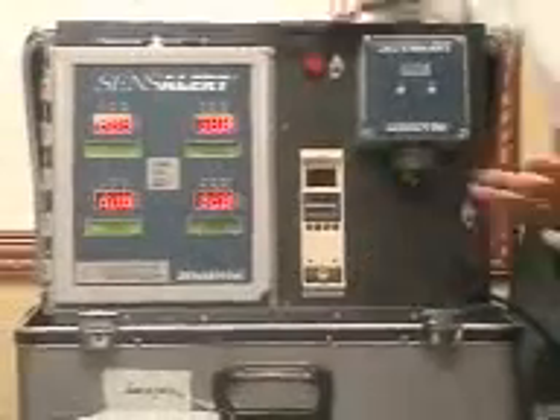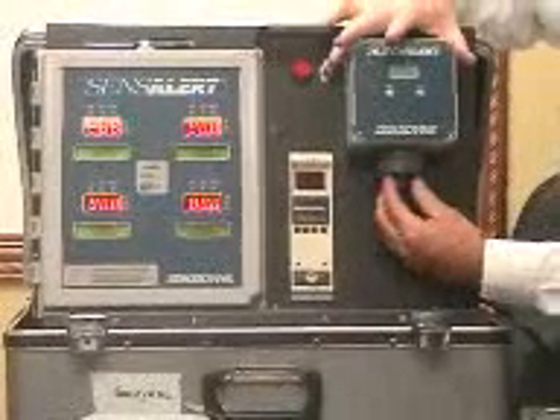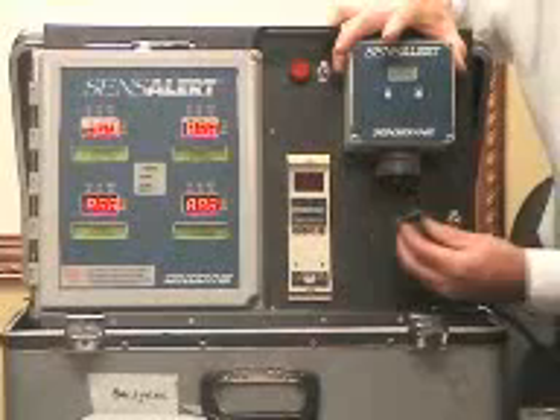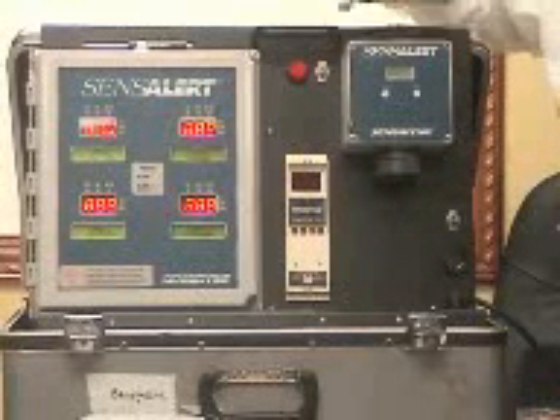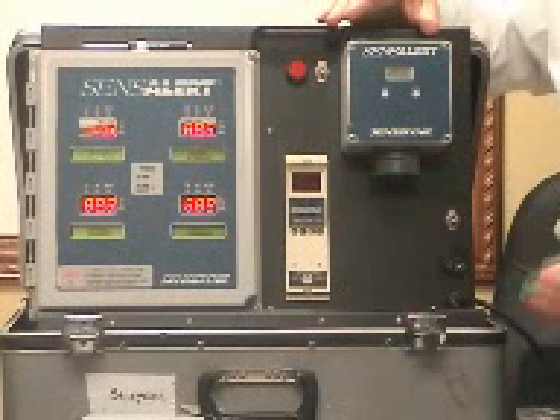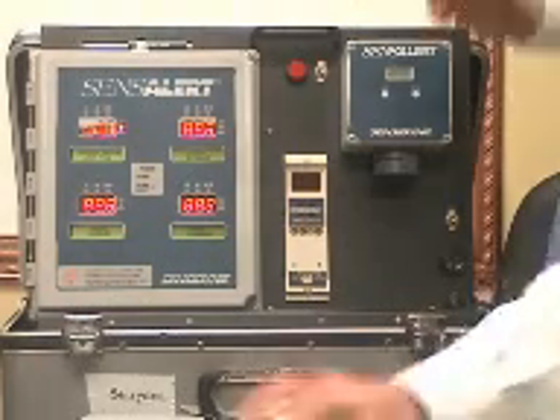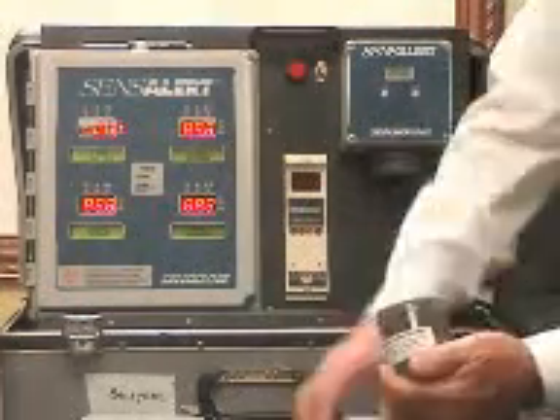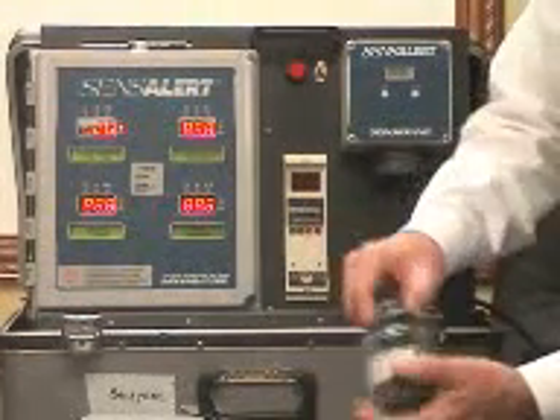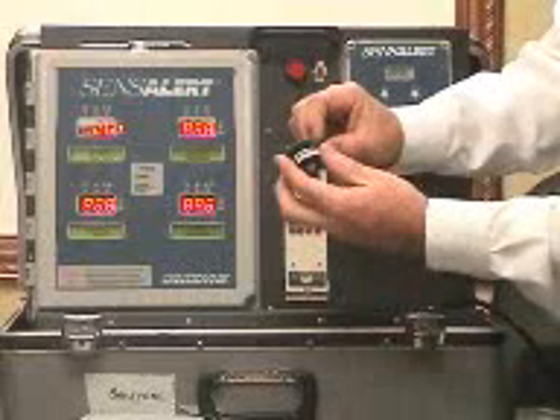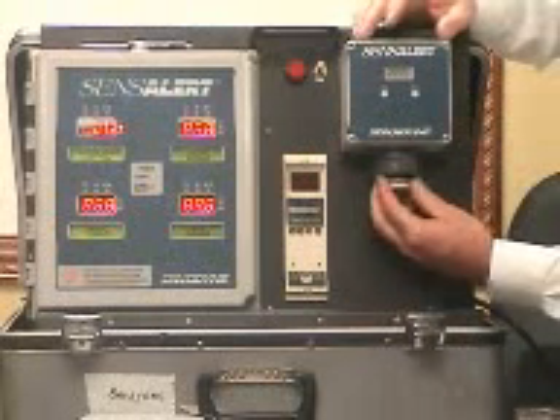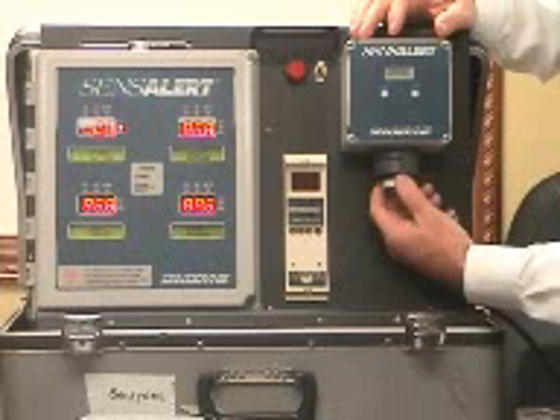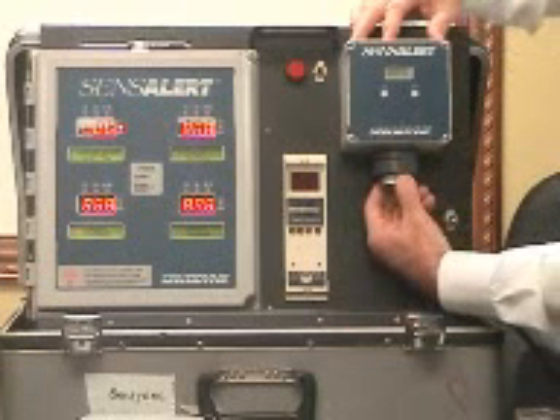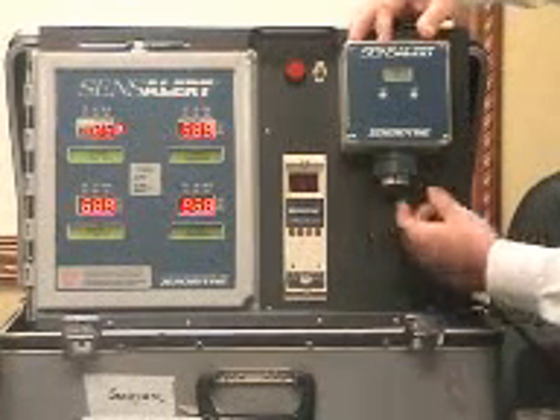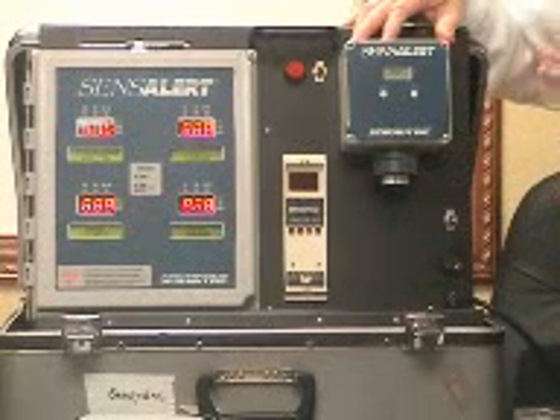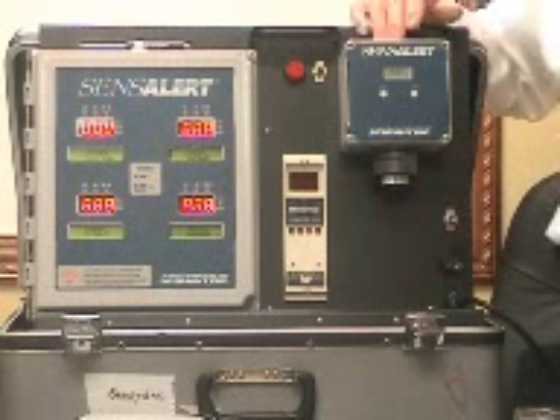And now I want to just show you how easy it is to change gas types. You just remove the sensor, and you can do this powered up. Say I'm going to put a combustible sensor in, and the other one we have is, I think, an ammonia sensor. Nice ammonia sensor. It's a real popular product. Put that in, turn it until it finds its seat, push it in. So you can't accidentally put it in backwards.